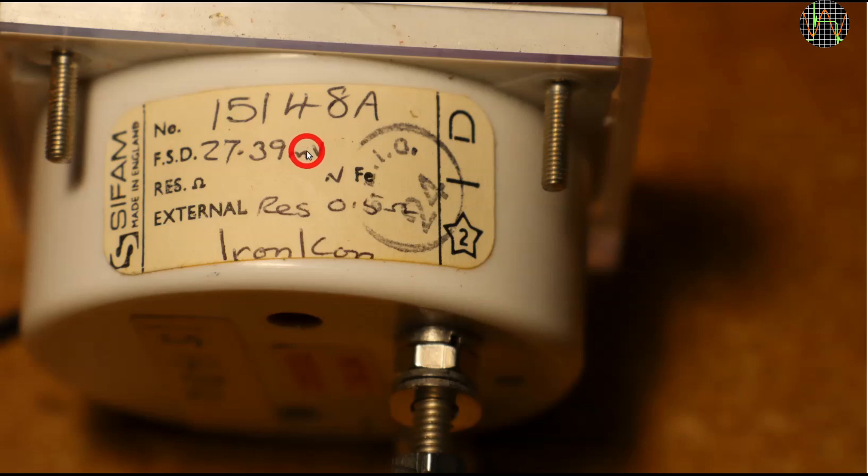I don't have the J-type formula or the NIST tables, but I have them for K-type thermocouples and for K-type the value for 500 degrees is 20.644 mV. I don't know what to make of the rest, especially what appears to say 0.5 Ohm. The bottom line stating Iron Con probably stands for Iron Constantan, which is of course what a J-type probe is made of.